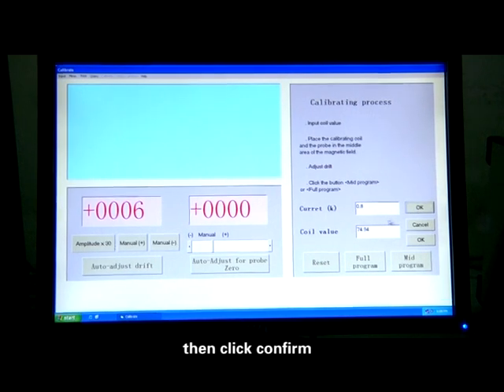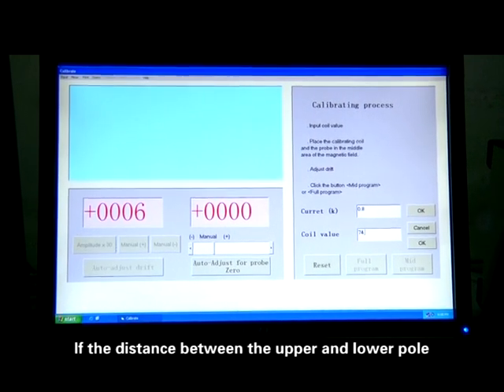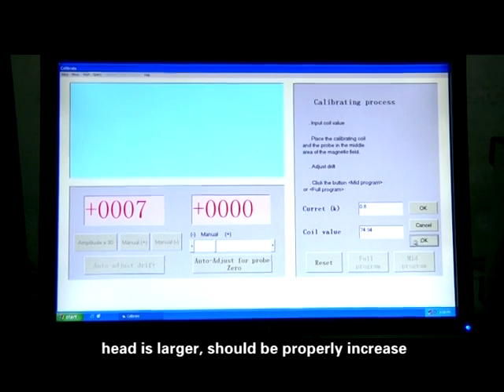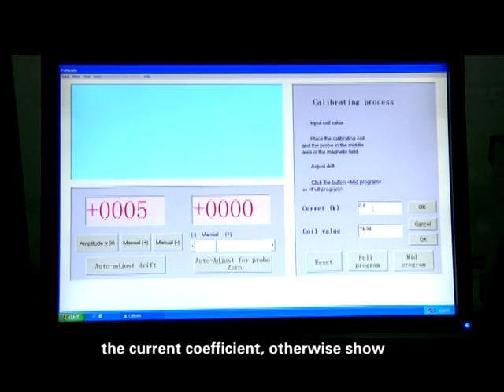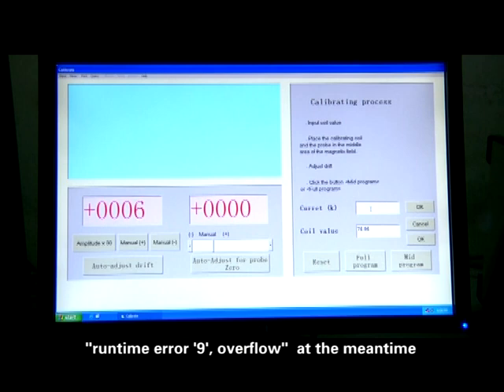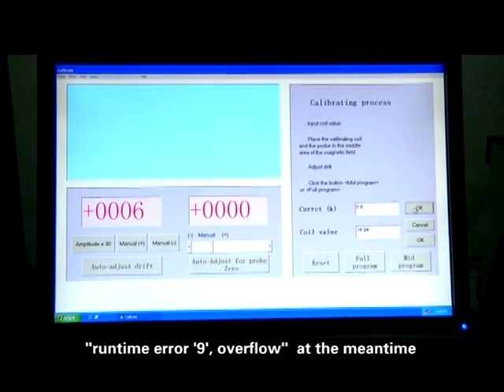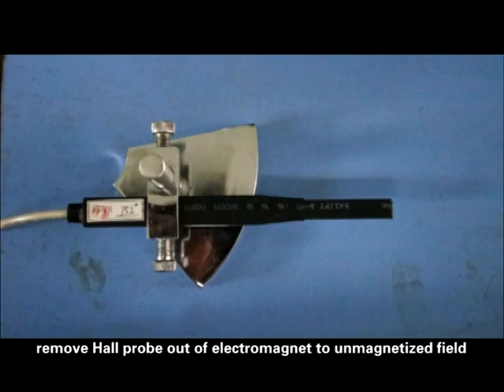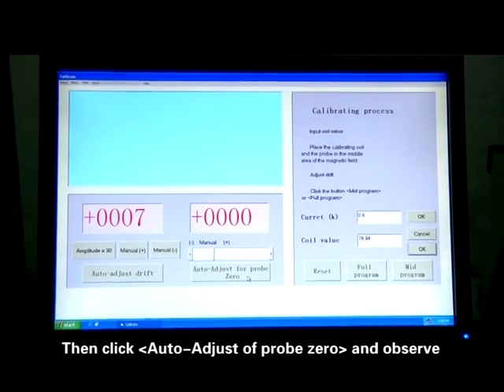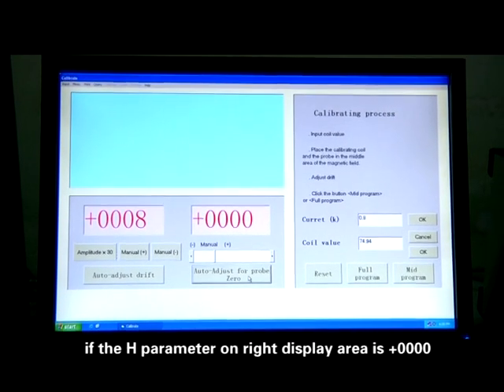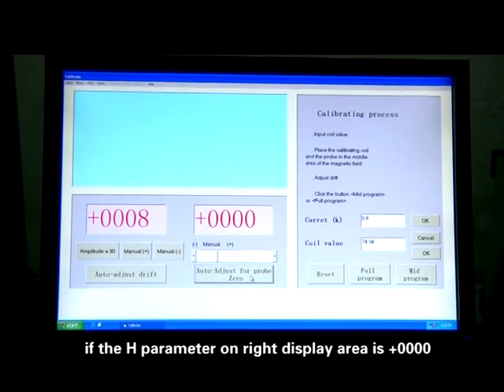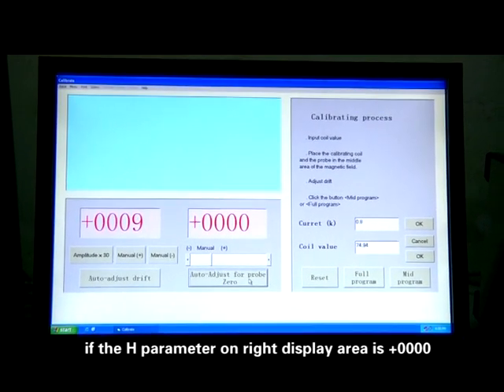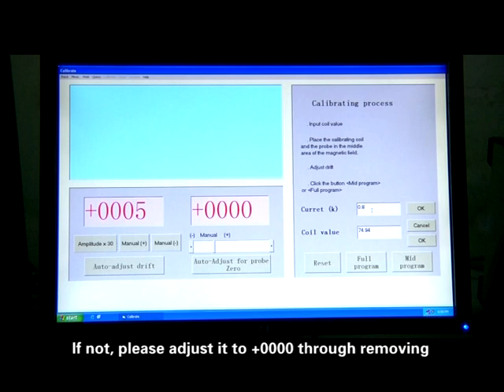Then click Confirm. If the difference between the upper and lower pole head is larger, should properly increase the current coefficient. Otherwise, it shows runtime error 9, overflow. At the meantime, remove Hall probe out of electromagnet to unmagnetize the field. Then click Auto Adjust of probe zero and observe if the H parameter on right display area is +0. If not, please adjust it to +0.